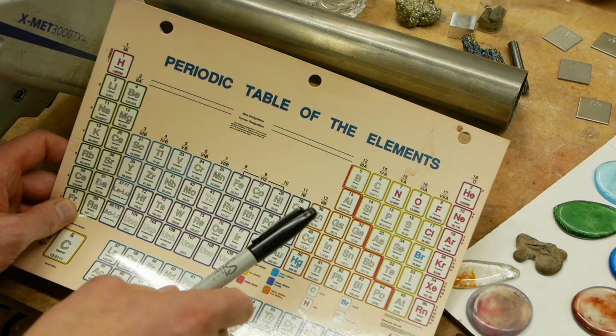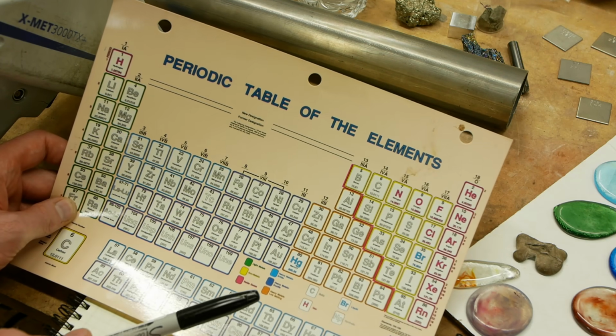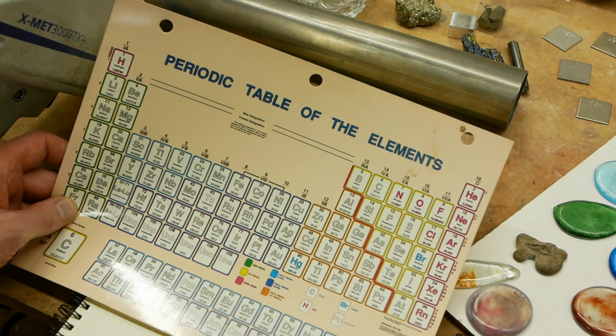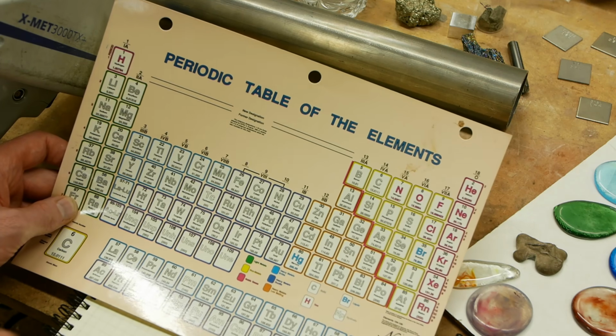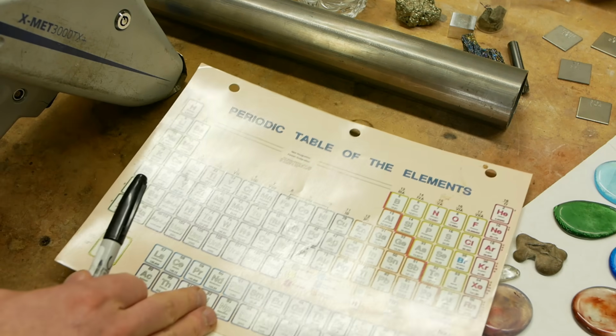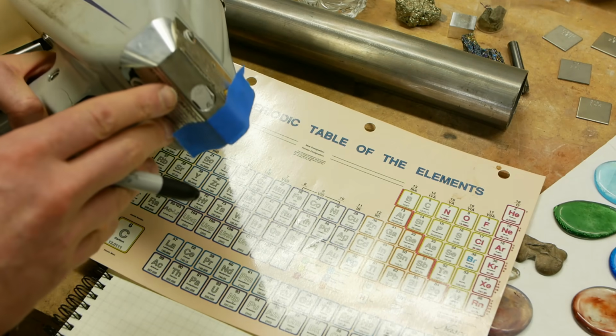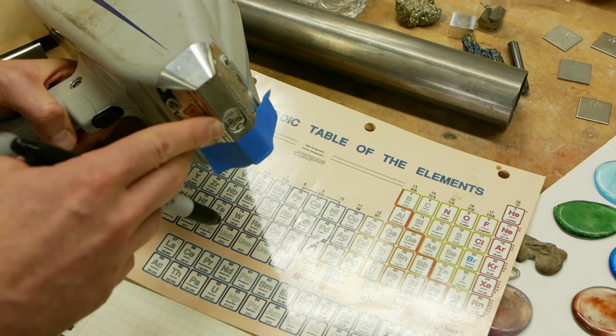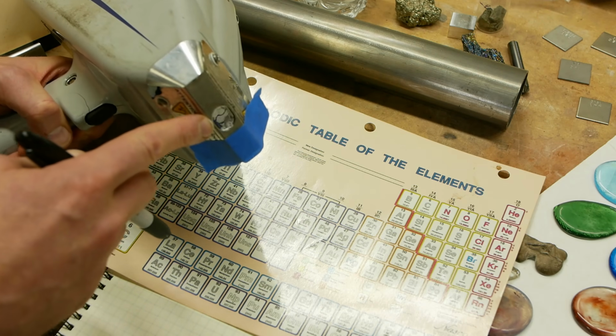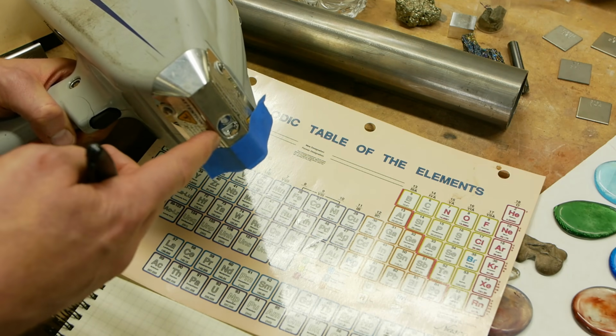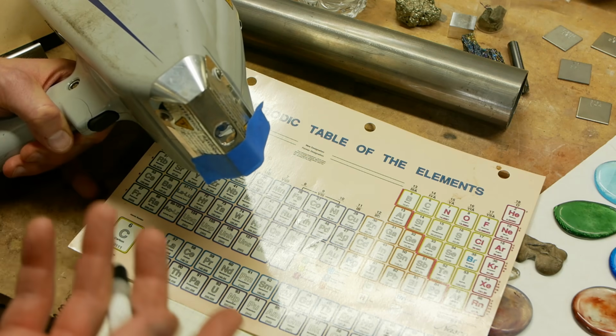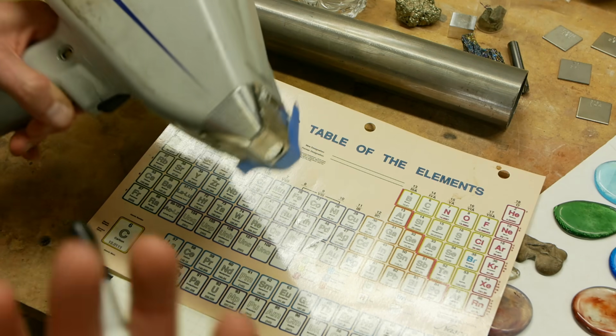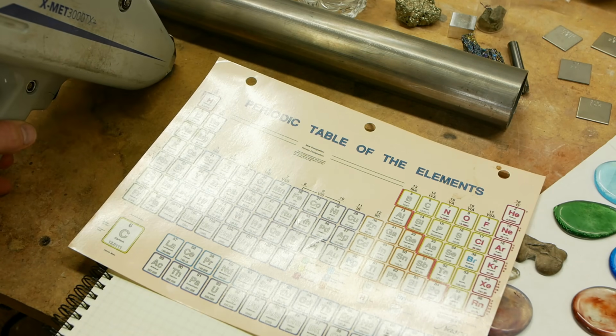But keep in mind that the heavier elements are easier to detect because they emit much stronger signals, and those strong signals penetrate all of the foils. Like, for example, the window on this thing is made of metal. It has this shiny metal window. So the return X-rays have to make it back through that window, and that means they have to be more intense than at least a couple kilo electron volts, say.